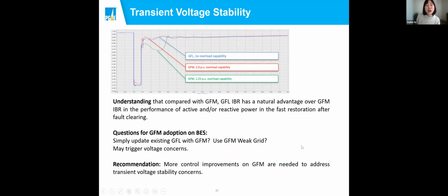And here, just to contemplate what we see in the voltage stability testing: the nature of the control in a grid forming inverter is different from grid following. So the recovery of the P and the Q is not very controllable. By testing the performance, there could be voltage concerns if we don't have additional control or improve the performance of P and Q from the grid forming inverter.